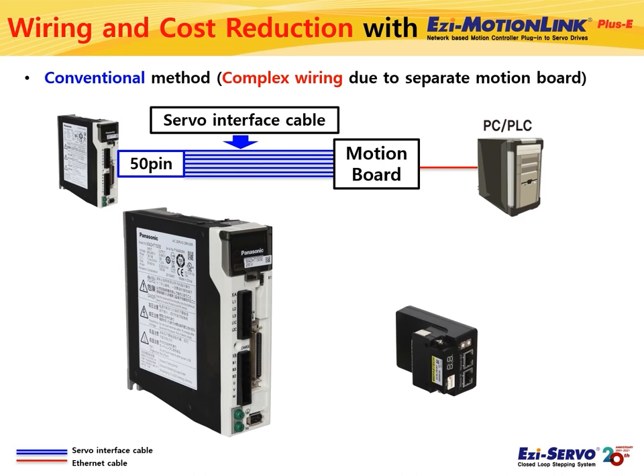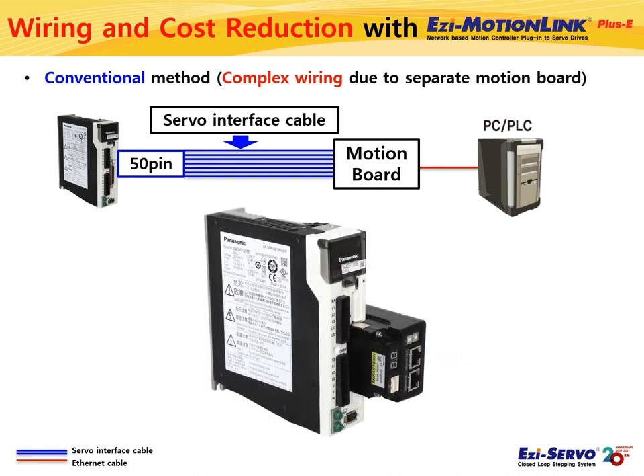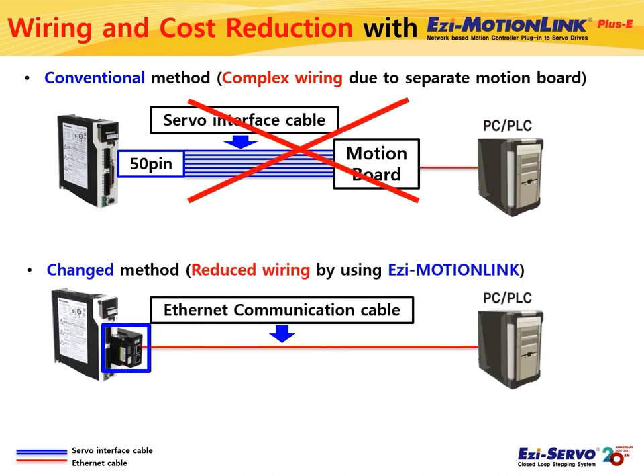For example, there is a Panasonic AC servo drive. Motion Link can be directly attached to the servo interface connector of this Panasonic AC servo drive. The servo interface connector of Panasonic AC servo drive is a 3M 50-pin connector, and most major AC servo drives also use this 3M 50-pin connector. Since Fastech Motion Link also uses this 3M 50-pin connector, it is compatible with most major AC servo drives. However, the pin map may be different for each AC servo drive — for example, the servo-on signal of Yaskawa AC servo is pin 5, while Mitsubishi is assigned pin 7, but the function of the interface is the same. With this, you can remove the complicated wiring bundle from the AC servo to the motion board. By using Ezi-MOTIONLink, a 1-axis motion controller, the customer can use 5-axis AC servo with only an Ethernet communication cable without a separate motion board. You can control these with the API that Fastech provides.